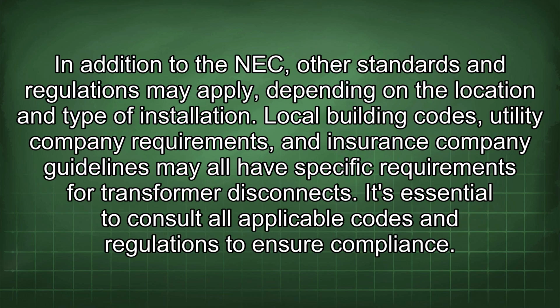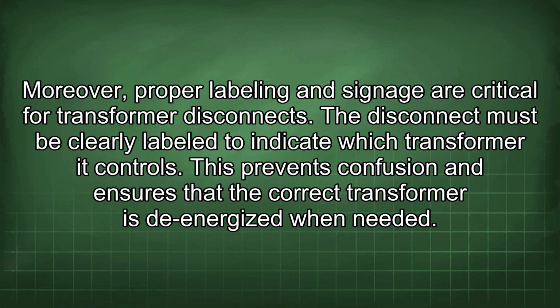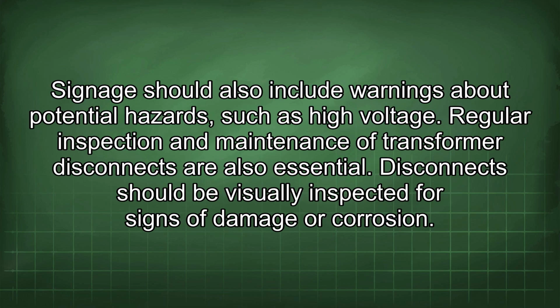In addition to the NEC, other standards and regulations may apply, depending on the location and type of installation. Local building codes, utility company requirements, and insurance company guidelines may all have specific requirements for transformer disconnects. It's essential to consult all applicable codes and regulations to ensure compliance. Moreover, proper labeling and signage are critical for transformer disconnects. The disconnect must be clearly labeled to indicate which transformer it controls. This prevents confusion and ensures that the correct transformer is de-energized when needed. Signage should also include warnings about potential hazards, such as high voltage.